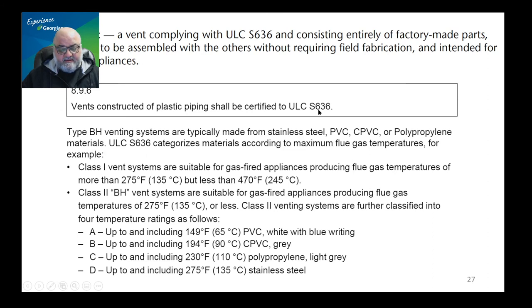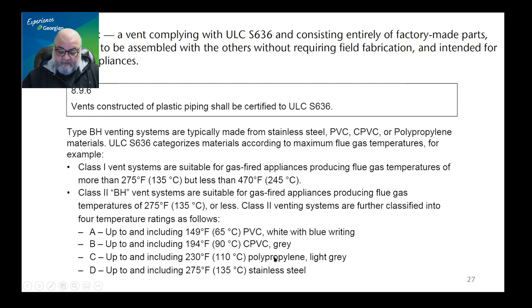What about ULC S636 that is not plastic? There are four temperature ratings in ULC S636. The first is up to 149°F, the second up to 194°F, and the third up to 230°F — all three of those are plastic: PVC, CPVC, and polypropylene respectively, each withstanding progressively higher temperatures. But once you go beyond that — for Type BH withstanding 275°F flue gas temperatures — it is only safe to use stainless steel.